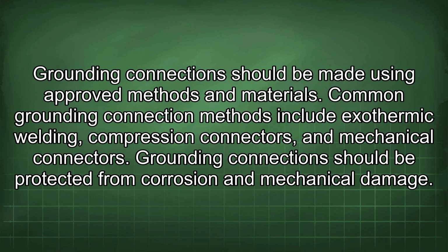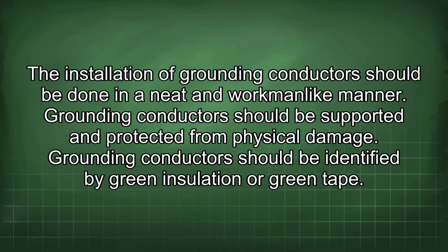Grounding connections should be made using approved methods and materials. Common grounding connection methods include exothermic welding, compression connectors, and mechanical connectors. Grounding connections should be protected from corrosion and mechanical damage. The installation of grounding conductors should be done in a neat and workmanlike manner. Grounding conductors should be supported and protected from physical damage. Grounding conductors should be identified by green insulation or green tape.